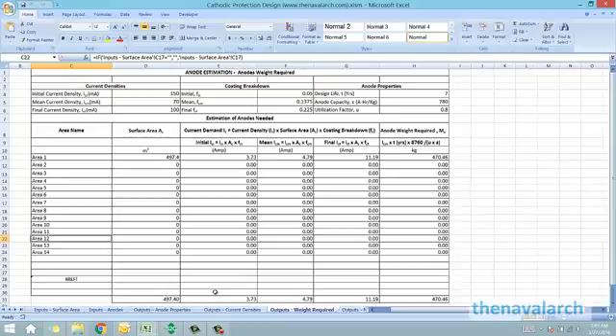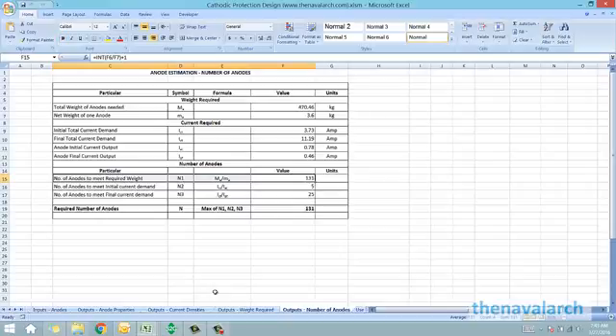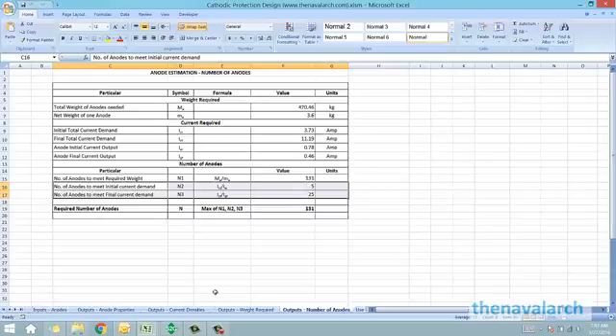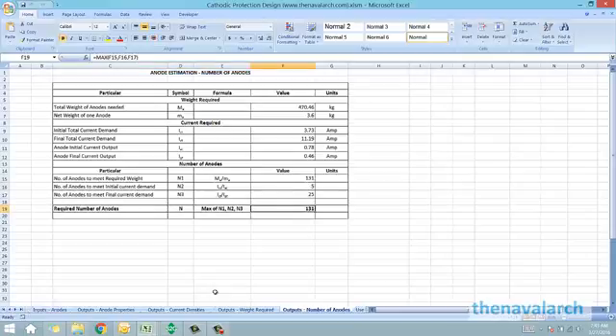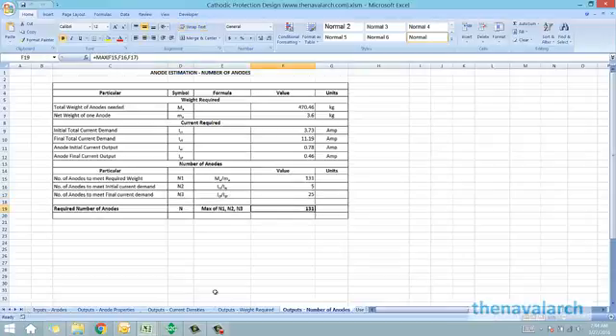Once we have the final current demands and the total weight of anodes required, we can calculate the total number of anodes. From the unit weight of the anode and the total weight required, we get one figure for the number of anodes. From the initial and final total current demands and the initial and final current outputs of a single anode, we get two more figures. The maximum of these three — anodes to meet the required weight, anodes to meet the initial current demand, and anodes to meet the final current demand — is the final total number of anodes required to protect all surfaces from corrosion.